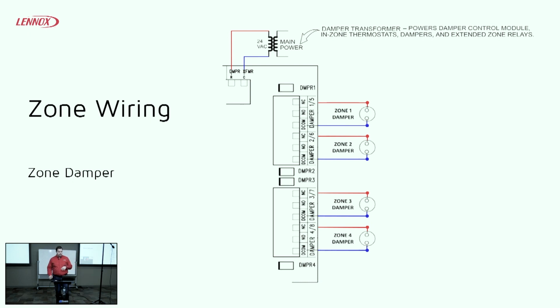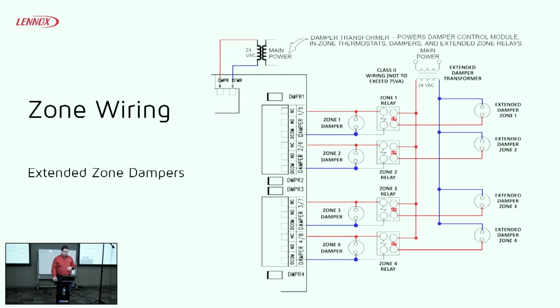Another critical point here is wiring in our zone transformer. We'll talk a little bit about phasing this, but that's an important step. This is the extended zone damper. Sorry, I don't think I had enough coffee this morning. This is so if you have a scenario where you've got, in this case, 8 zone dampers. This shows how to tie in a secondary transformer if need be, using isolation relays. This is a diagram that's in the manual, but it's an option that's out there if you're using a lot of dampers. Any questions so far?